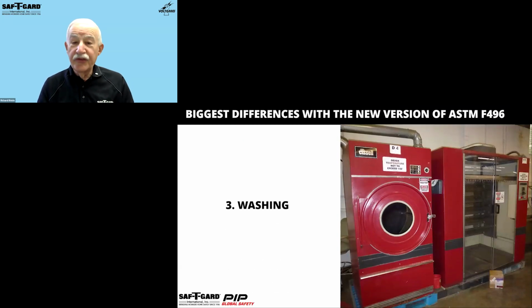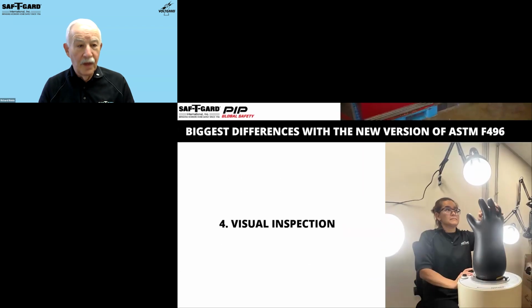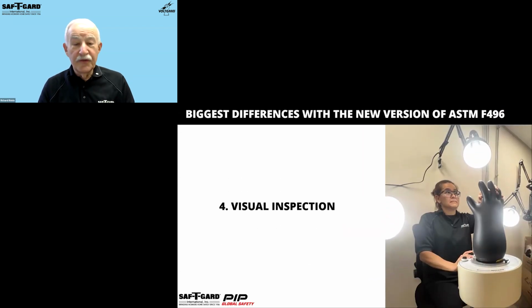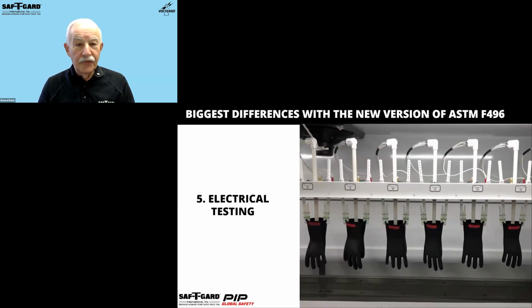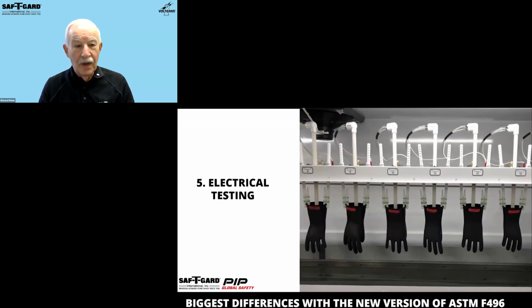Washing using cleaning agents that will not degrade the rubber insulating properties. Visual inspection of all surfaces inside and out to be sure that there's no physical damage to the rubber gloves. A visual failure is an electrical failure waiting to happen. So we recommend a visual inspection every day before use and then before electrical testing at a qualified test facility. Then there's the electrical testing on that unique equipment that's designed for that purpose.